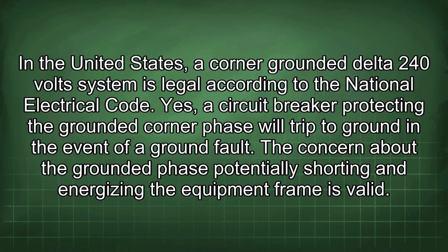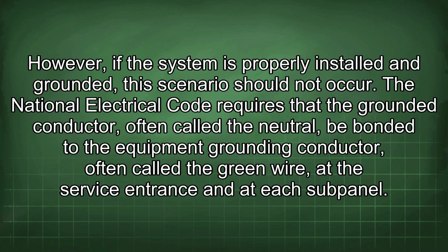In the United States, a corner-grounded delta 240-volt system is legal according to the National Electrical Code. Yes, a circuit breaker protecting the grounded corner phase would trip to ground in the event of a ground fault. The concern about the grounded phase potentially shorting and energizing the equipment frame is valid. However, if the system is properly installed and grounded, this scenario should not occur.